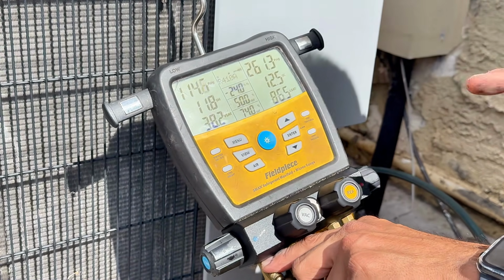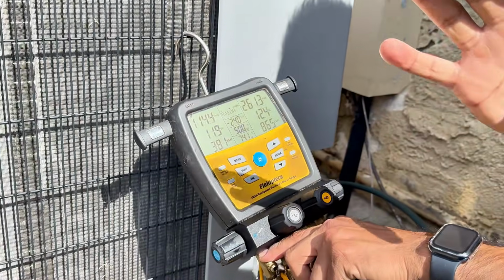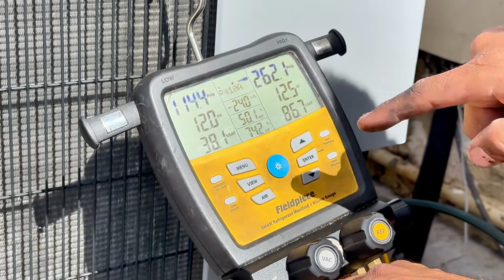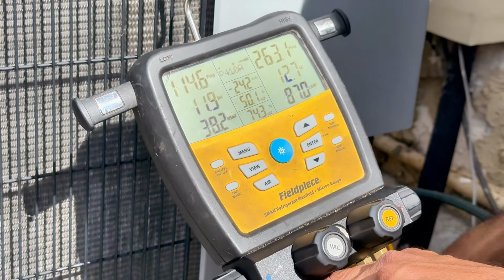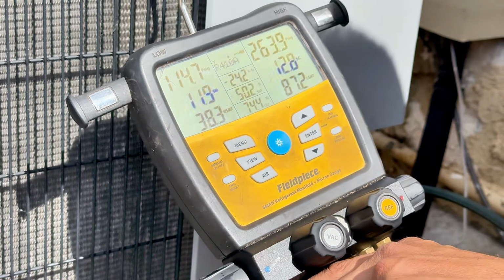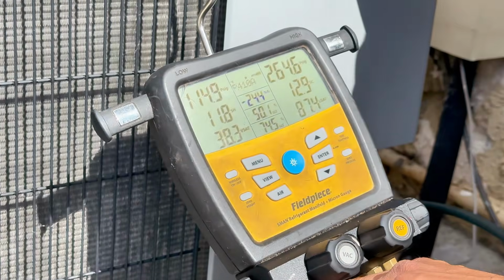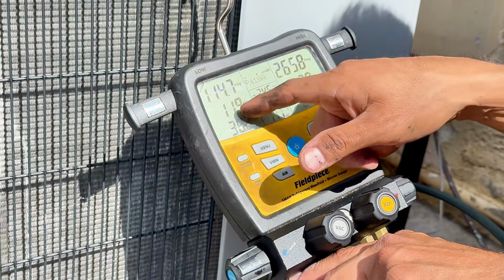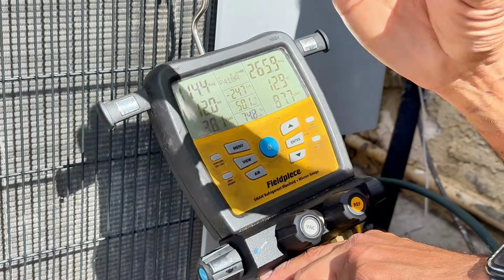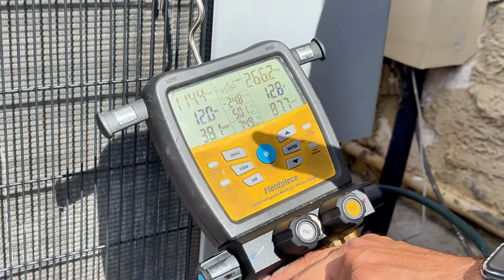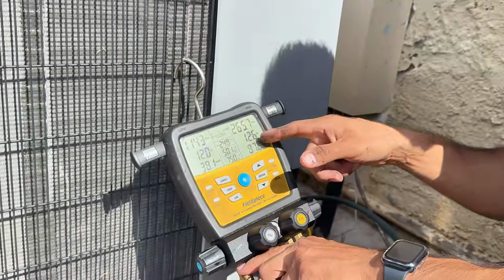That looks pretty good. What I'm looking at is my superheat and subcool. My suction line temperature is 50 degrees and my liquid line temperature is 74.2. Look at my superheat. It's a TXV, so it's maintaining a superheat of between 8 to 14. I'm at 12. That looks great. But for a system with a TXV, you're looking at subcool.